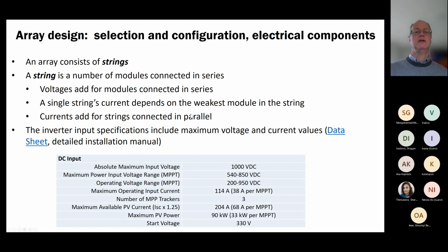That's what's indicated here. So the inverter that you choose will have specifications for the maximum voltage and the maximum current values. And you can see here, for example, the absolute maximum input voltage, 1000 volts DC. The maximum operating input current, 114 amps. The maximum potential or available PV current, 204 amps.